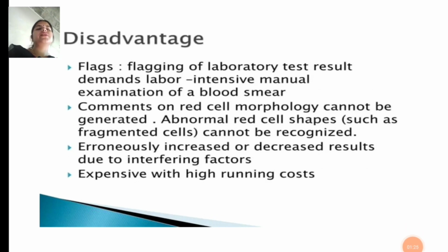Next are the disadvantages of automation in hematology. The flagging of laboratory test results demands labor-intensive manual examination of a blood smear. Comment on red cell morphology cannot be generated. Abnormal red cell shapes, such as fragmented cells, cannot be recognized. Errors may occur, with increased or decreased results due to interfering factors. It is expensive with high running cost.